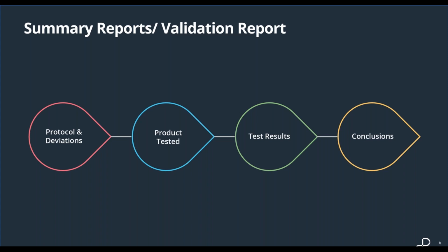So you should fully have characterized where those potential use-related issues are going to be. In order to facilitate an FDA review, for example, the materials that you've used in that process, including portions of risk analyses focusing on user interactions with the device, specific risk analysis processes, results, and those conclusions should all be included in the report.